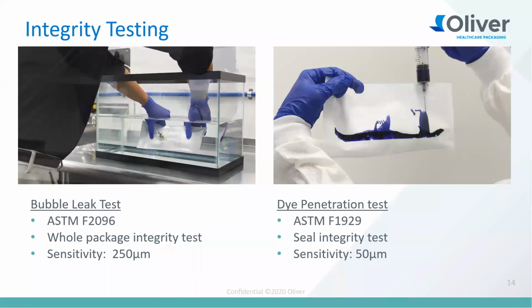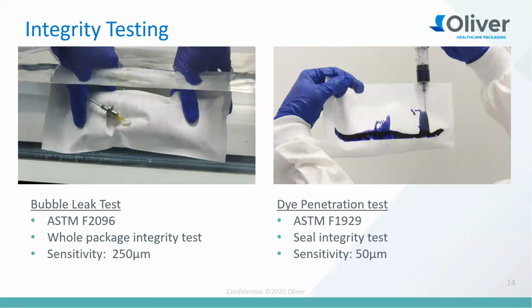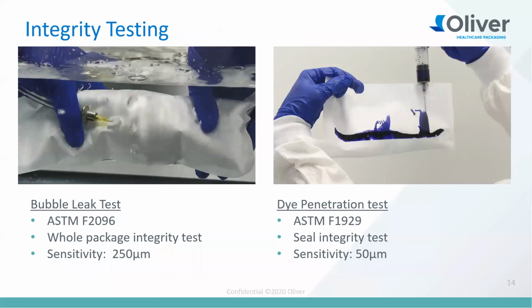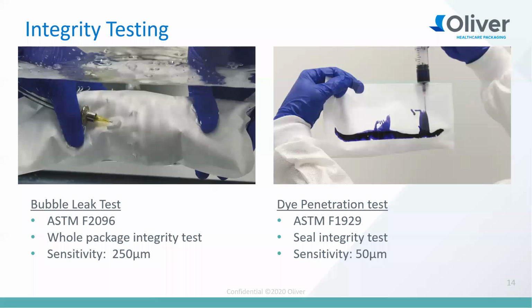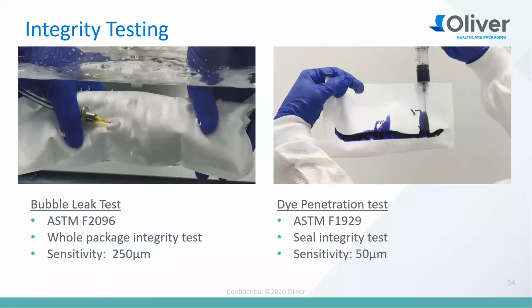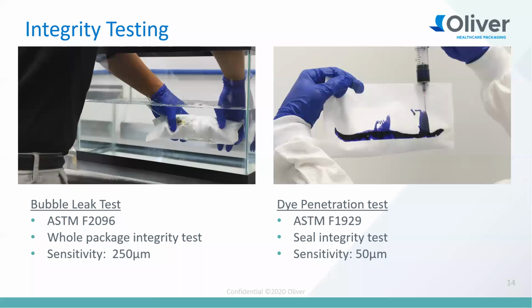And as mentioned earlier in the intro, we're performing integrity testing after that. So the first video you're seeing is a bubble leak test. This is based off of ASTM F2096. And this is a whole package integrity test. So you're submerging the package underwater, filling it with air, and looking for a constant stream of bubbles, as you saw in the video. The sensitivity of this is down to 250 micron. So if you have any pinholes after that, this is one of the most important parts. You're putting it through all the shipping, you see it dropping, vibrating. You really can test to see if any kind of pinhole or sterile barrier breach has occurred in this step.